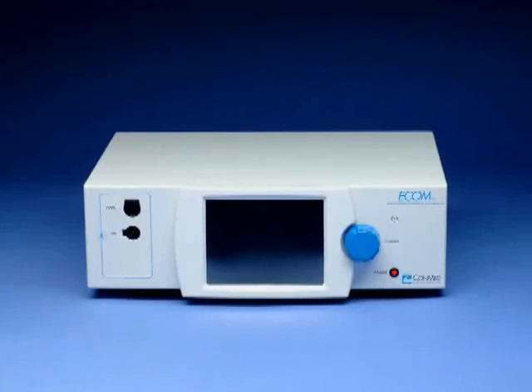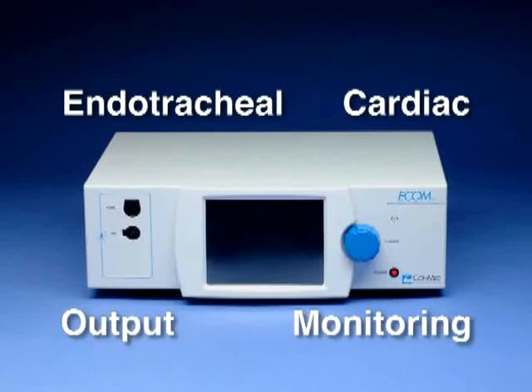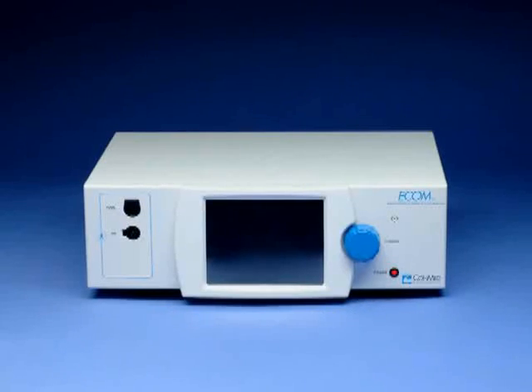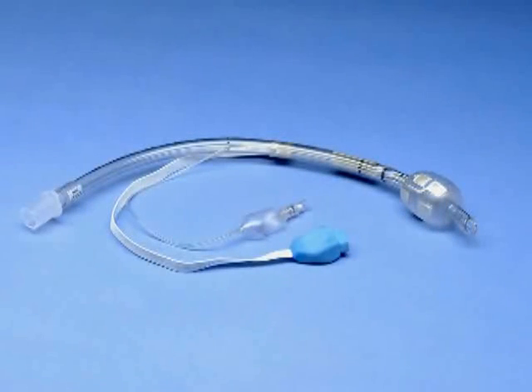This video introduces a new concept of endotracheal cardiac output monitoring, or ECOM, that has the potential of fulfilling these requirements. By using the principle of bioimpedance, cardiac output can be measured safely and reliably using a standard endotracheal tube. The ECOM system records voltages produced by a low-frequency current delivered to the tracheal mucosa by electrodes on an endotracheal tube. The proximity of the ascending aorta and trachea allows the design of a device that can optimize the current delivery and signal recording from impedance changes in the ascending aorta.